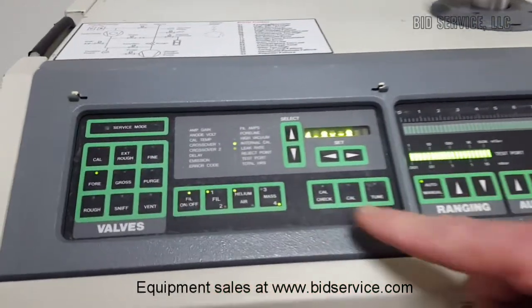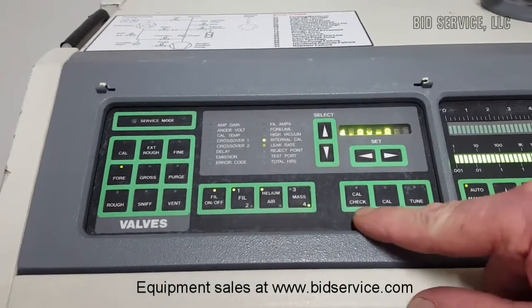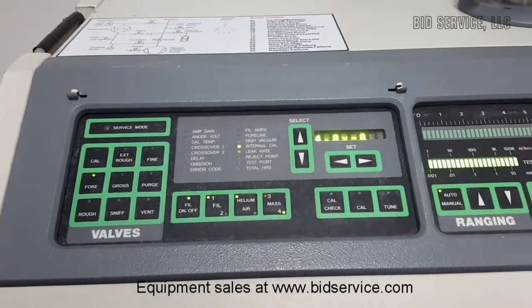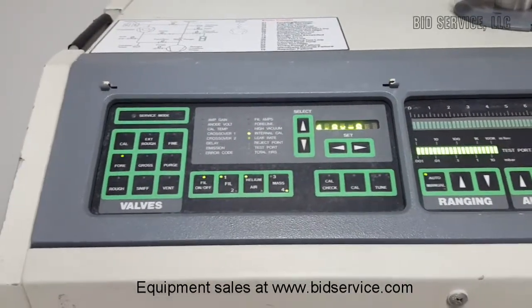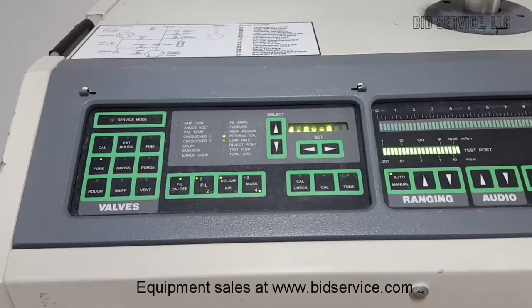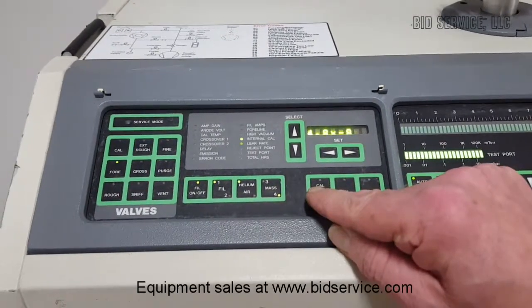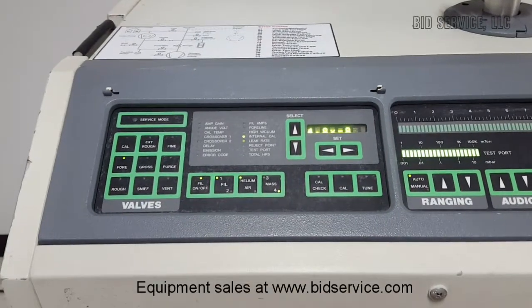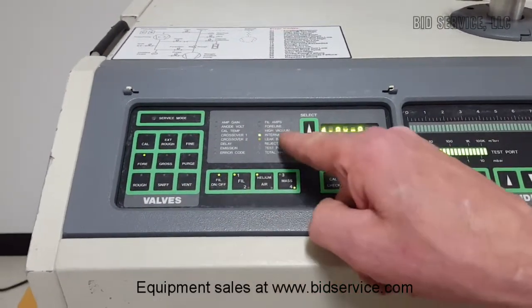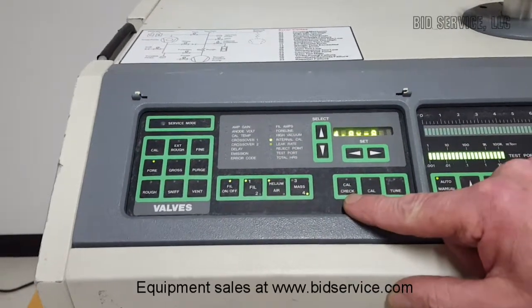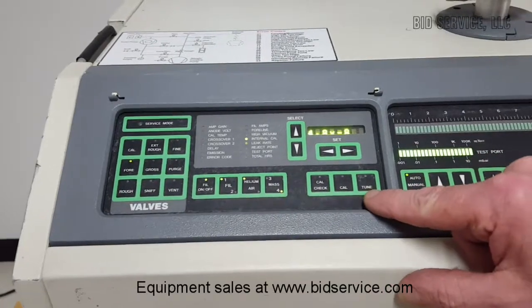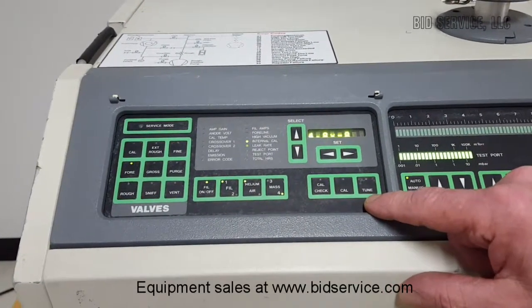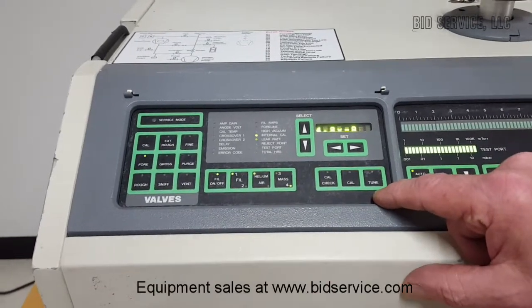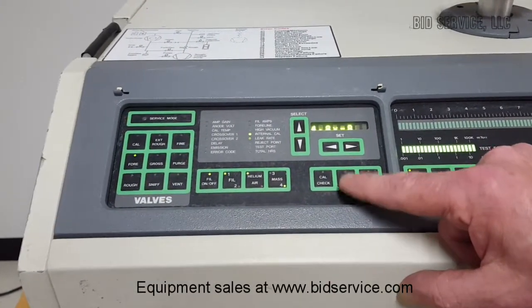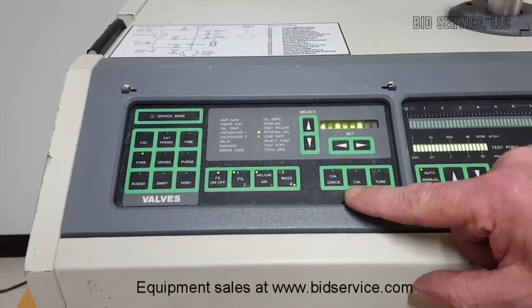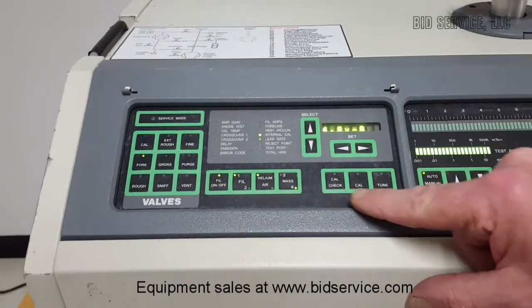The only exception to that are these three keys right here: CalCheck, Cal, and Tune. It is suggested by the manufacturer that once a day when using the equipment, especially after it's been powered down for a while, you do a CalCheck, which will check to see if you're still within the calibration range of the internal calibration. If the calibration is correct, then you can tune to your specific workpiece, and if that in any way is out of range, it would then allow you to calibrate specifically. The calibration key will not work on its own unless you first perform a CalCheck followed by a tune.